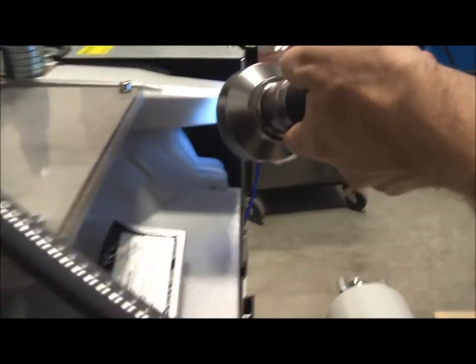We come around, we look in the hole and we watch it spinning down. It's spinning and it was going down, and that is with the arrow that's on the side of the pump. That is going the correct direction, and that's very important. You might want to have two people just double check that.